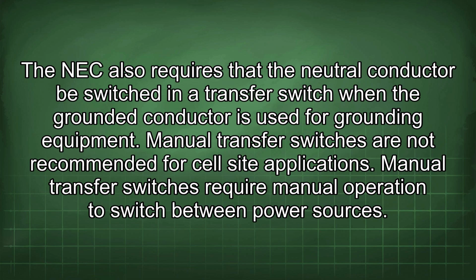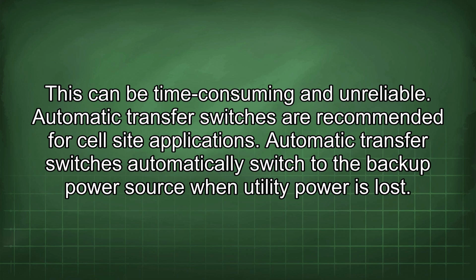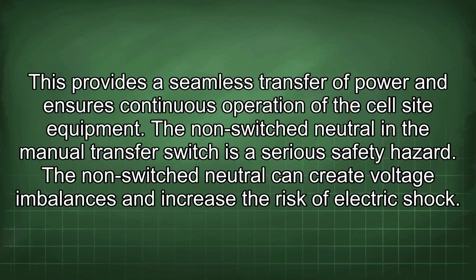Manual transfer switches are not recommended for cell site applications. Manual transfer switches require manual operation to switch between power sources. This can be time-consuming and unreliable. Automatic transfer switches are recommended for cell site applications. Automatic transfer switches automatically switch to the backup power source when utility power is lost. This provides a seamless transfer of power and ensures continuous operation of the cell site equipment.